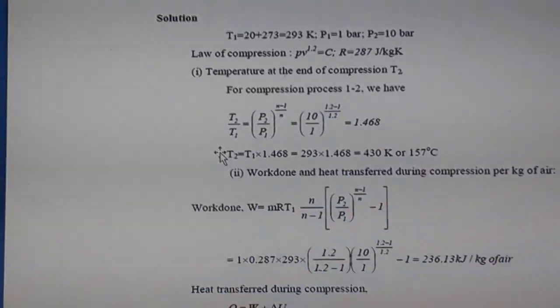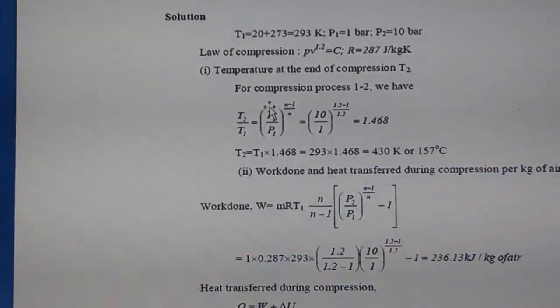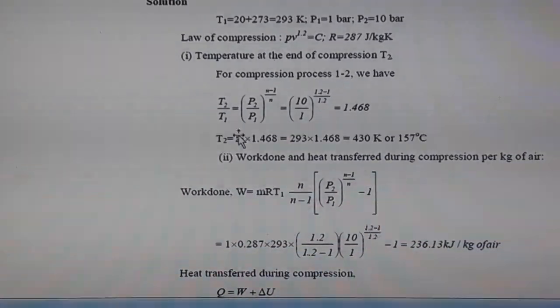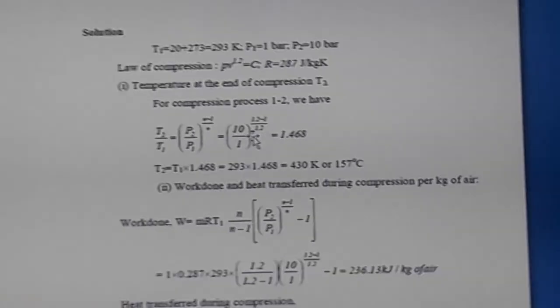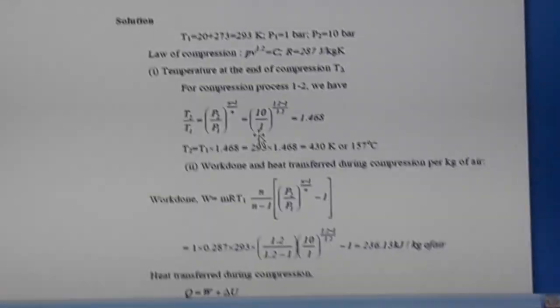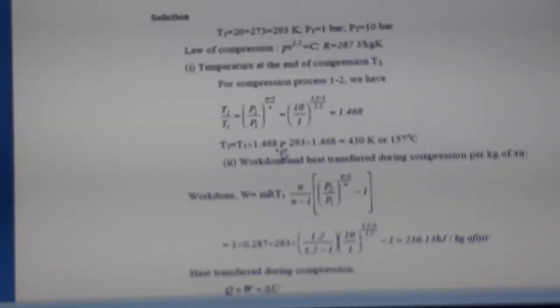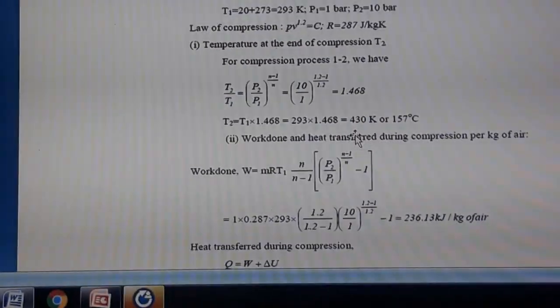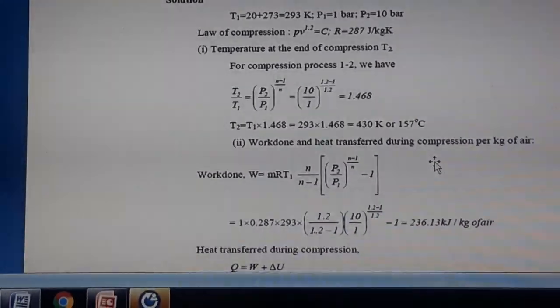To find temperature T2, use T2/T1 = (p2/p1)^((n−1)/n). With T1 = 293 K, p2/p1 = 10/1, and n = 1.2, we get T2 = 430 K, or 157°C.